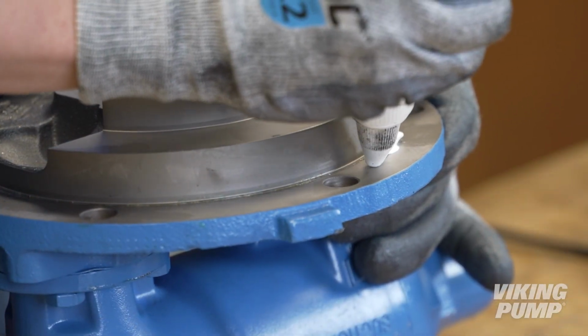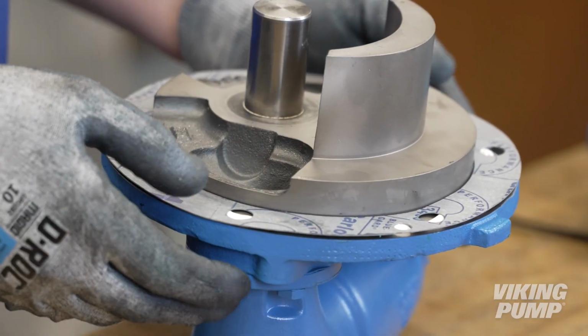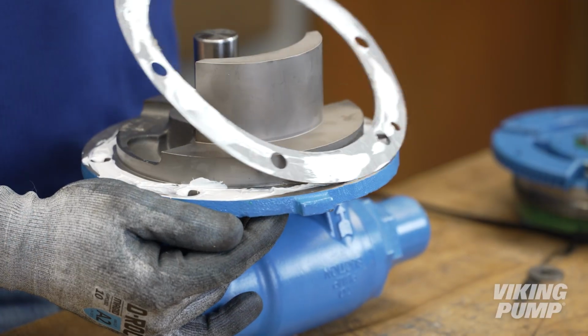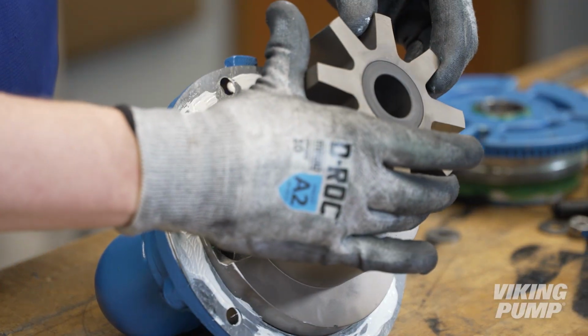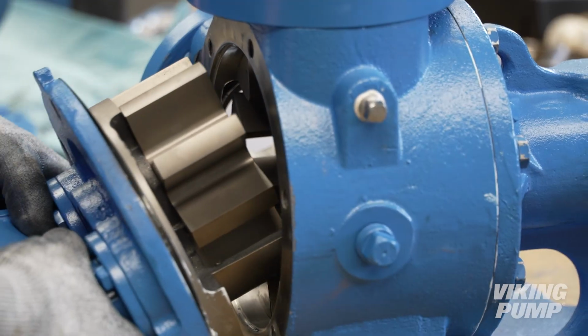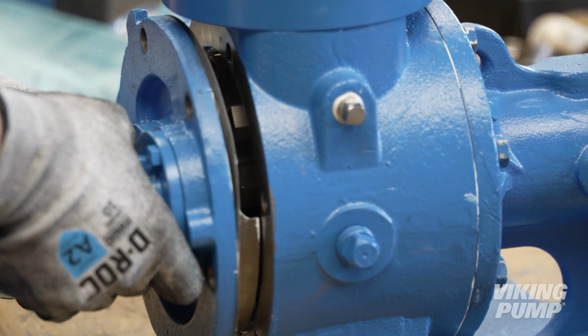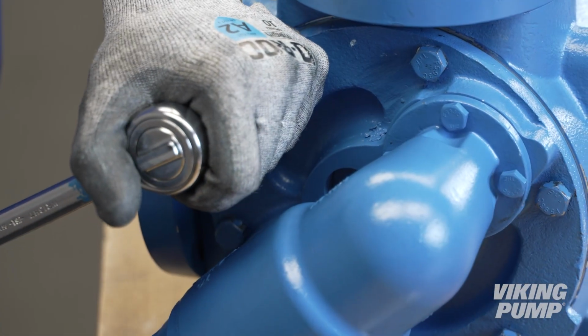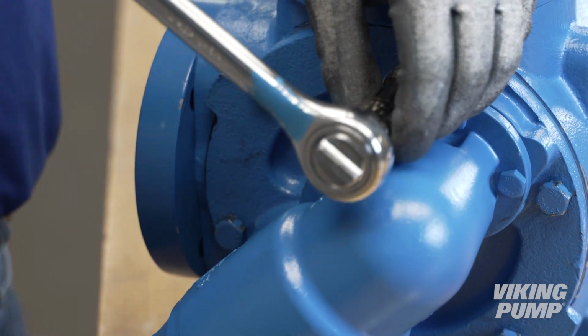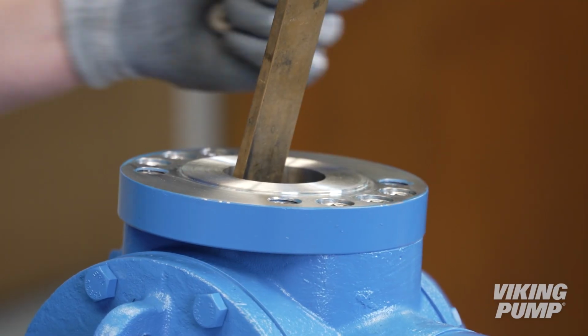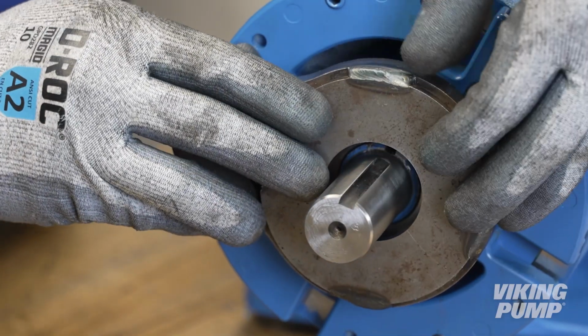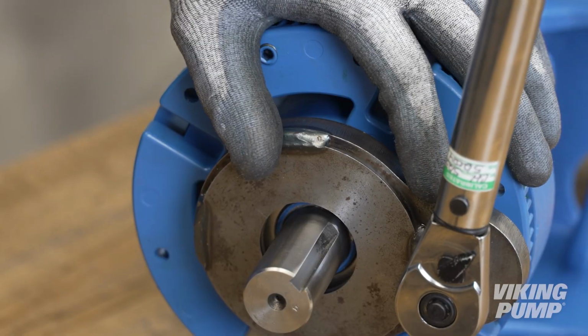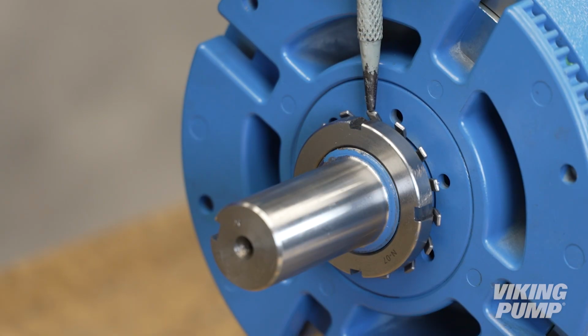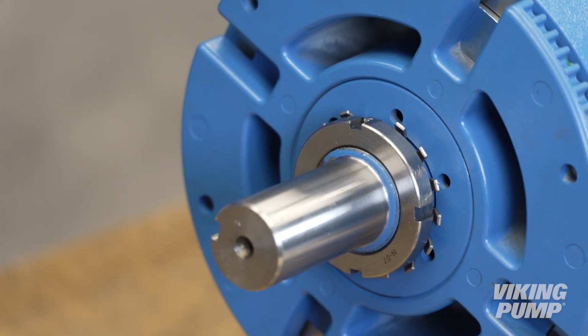Install the head gasket. Apply appropriate gasket sealant to the head and ensure even coverage on both sides of the gasket. Install the idler onto the idler pin. Install the head. Ensure that the relief valve is oriented toward the suction port. Place a brass or hardwood bar into the port opening to keep the pump from turning. Torque the lock nut to the appropriate torque setting. This setting can be found in the technical service manual. Bend a tang of the lock washer into a slot of the lock nut. If no tang aligns, continue to tighten the lock nut until one does. Failure to tighten the lock nut or engage the lock washer tab could result in early bearing failure and cause damage to the rest of the pump.